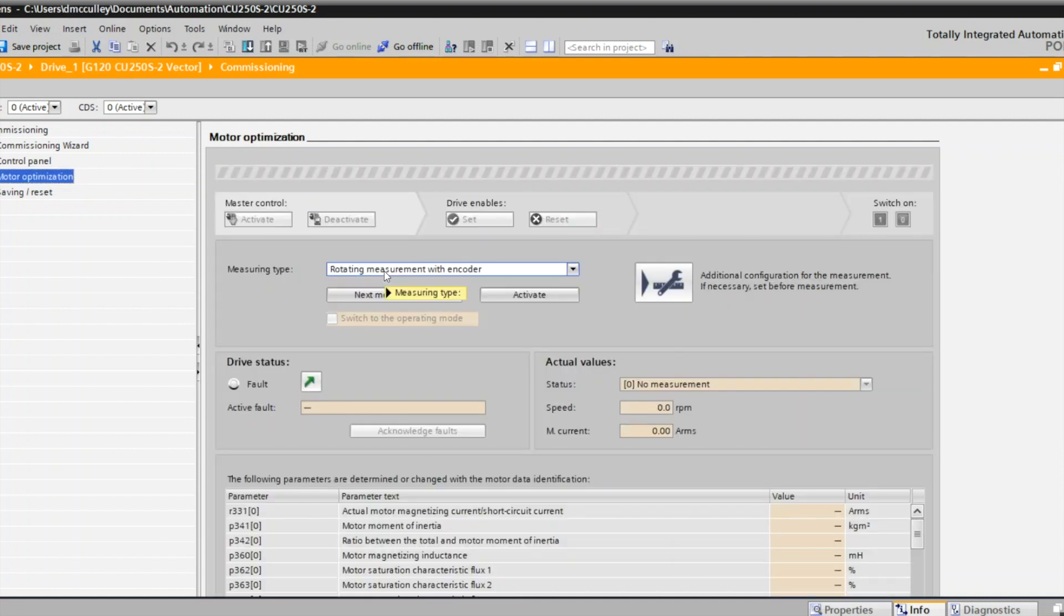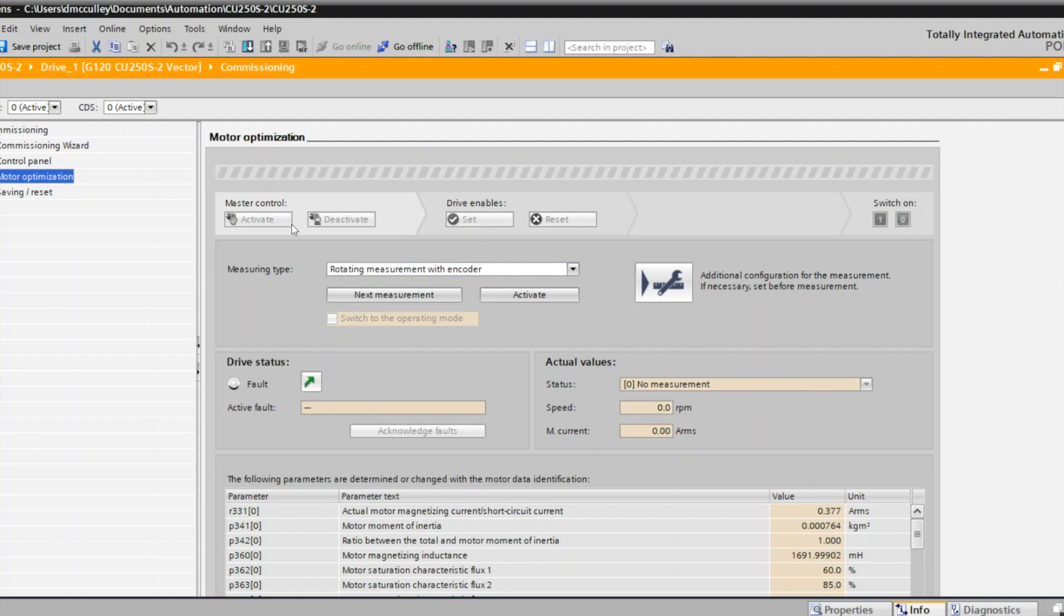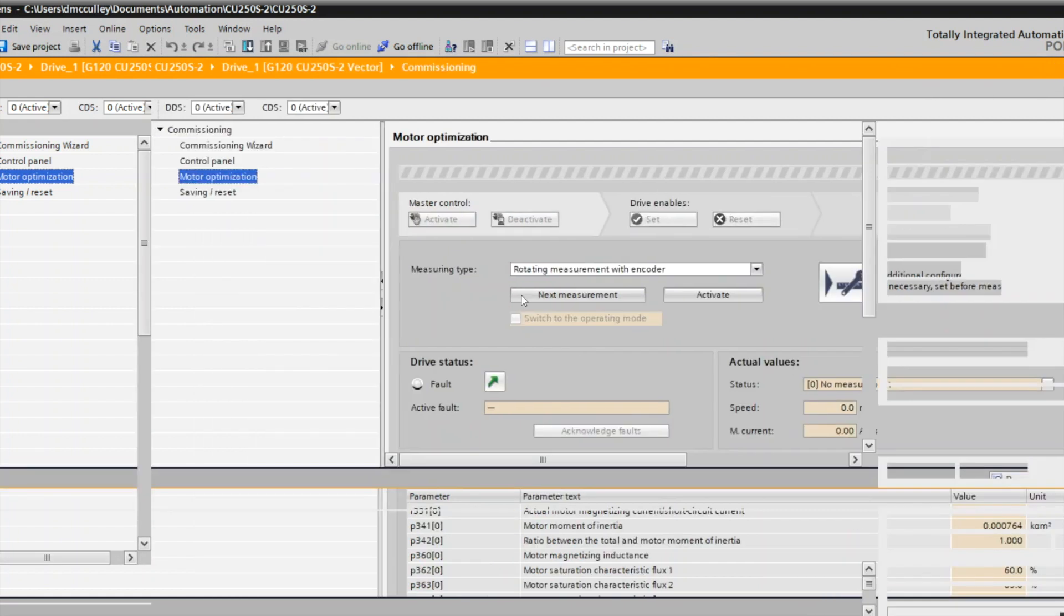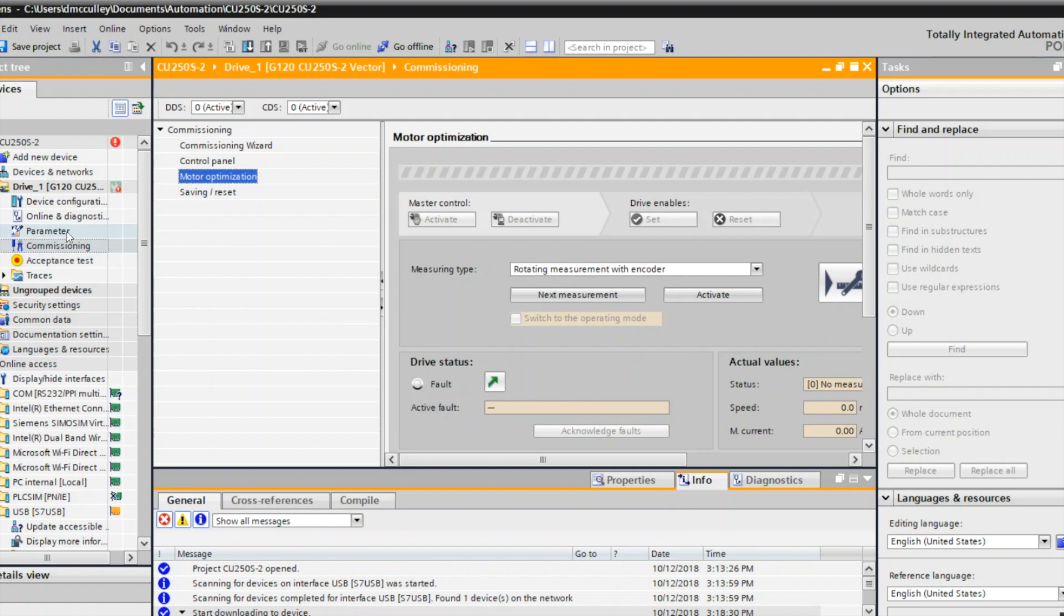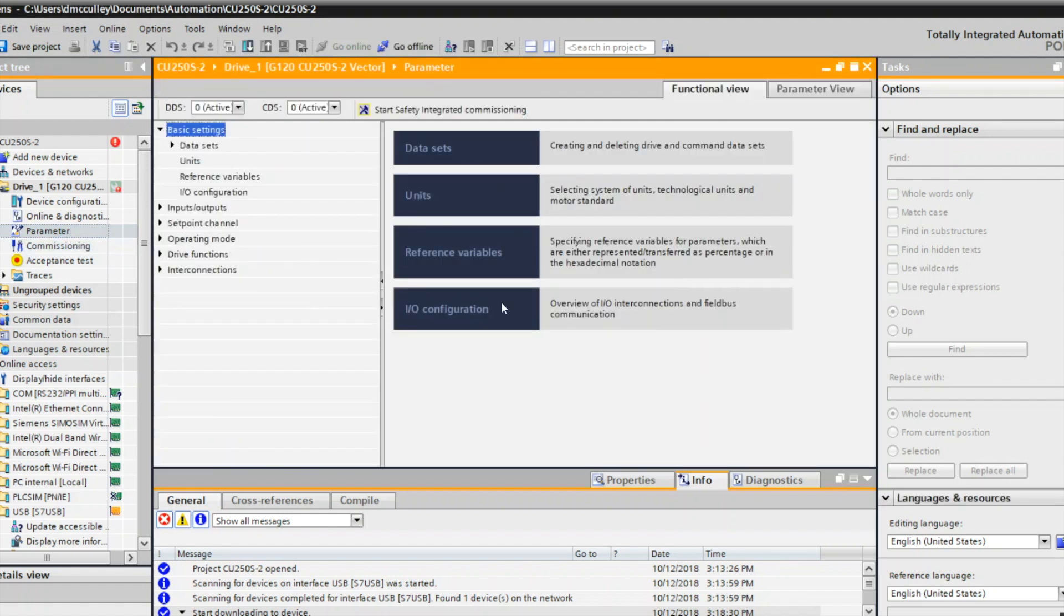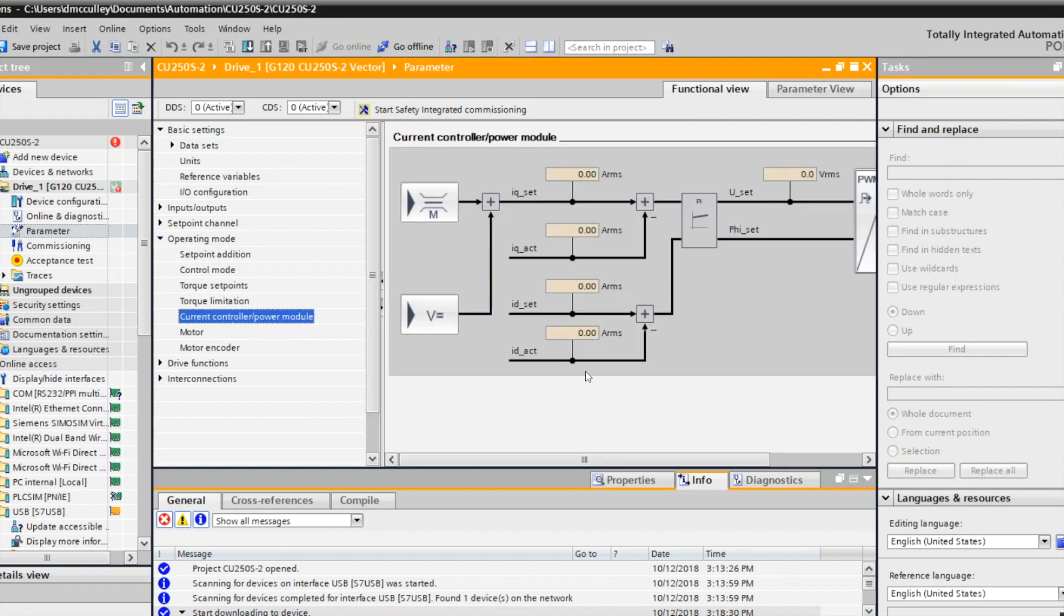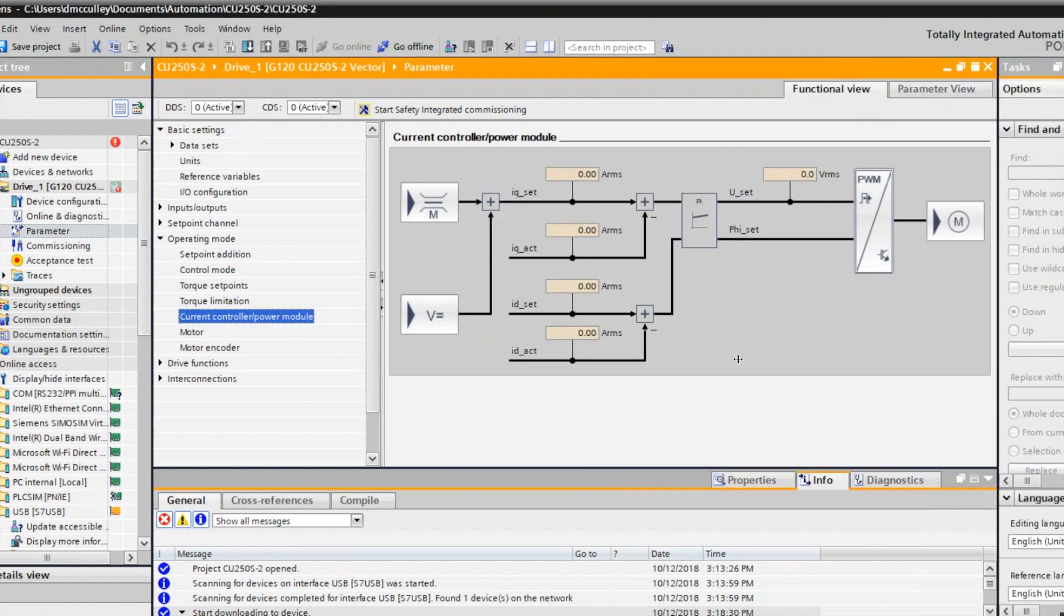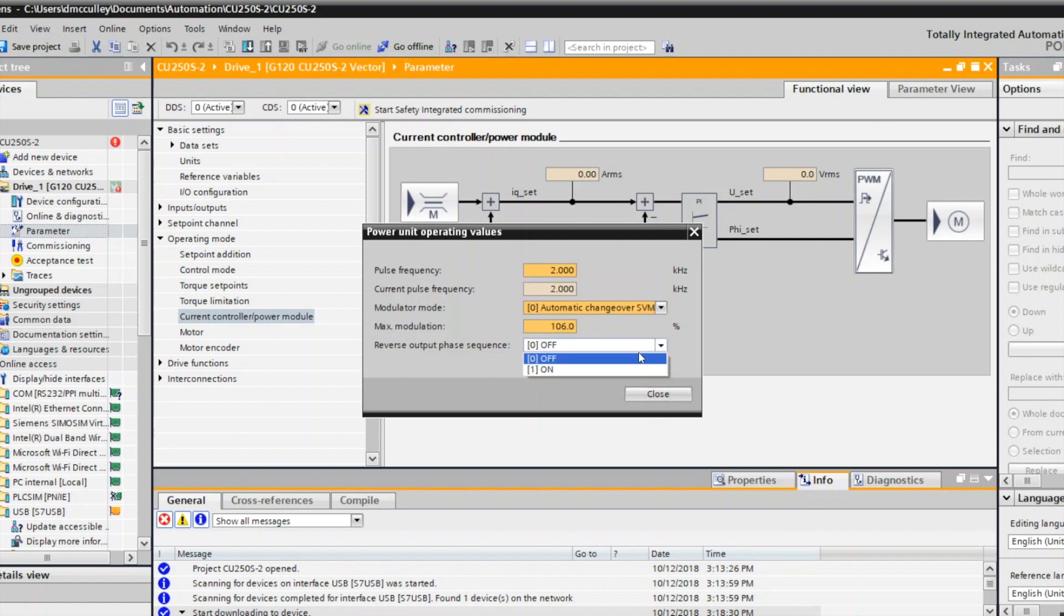Now the drive and motor are ready to run. The other thing you may need to be concerned about is if the motor is turning in the correct direction. If it's not, then you can actually change that in the parameter set. We'll go to parameters and operating mode and current controller power module. Under pulse width modulation, there's this reverse output phase sequence, which would be the same as reversing two leads on the motor. So it'll make the motor rotate in the opposite direction for a forward command. If you need to do that, you can turn that on.